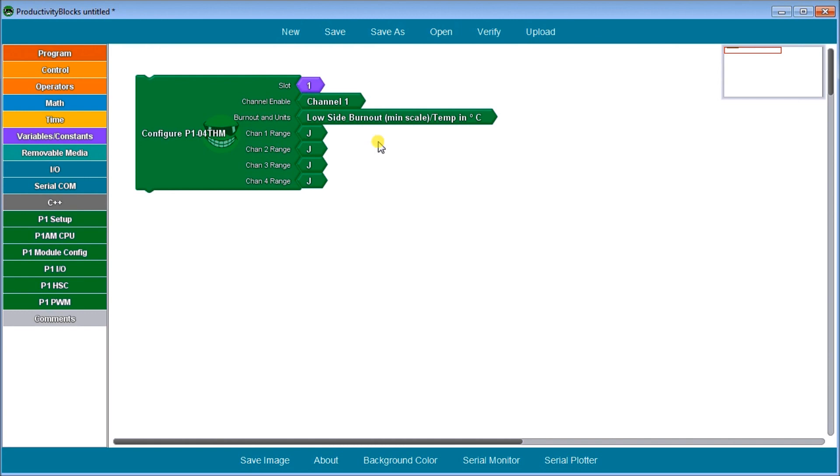To actually read in Productivity Blocks, we use the P1 IO and then select read temperature. We look at the slot and the point. Because this is a four-channel module, it will be point one, two, three, or four to get that information in. Even if we have voltage selected as our input, we still use the Productivity Blocks read temperature block to get that information into our controller.